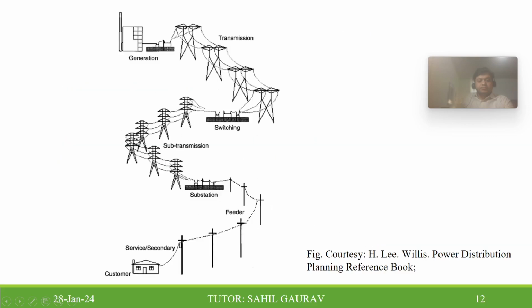You can also refer to this diagram. From there you can see the transmission system, and this is the generating power plant. Then we have the substation, the switching substation, then the sub-transmission system comes, and then we have the distribution substation. Then this is the primary distribution system, represented here as the feeder, and it connects to the distribution transformer, where we have the secondary distribution network. So this is a very nice picture that demonstrates the system from the higher level to the lower level.